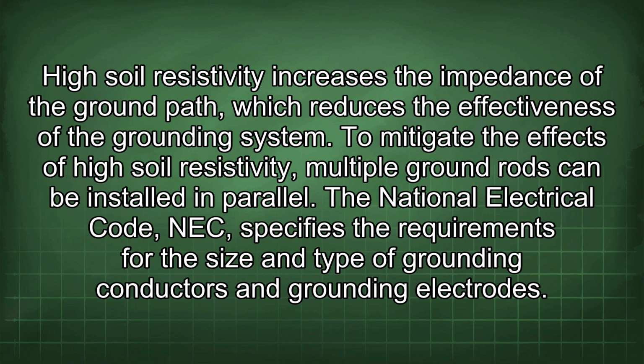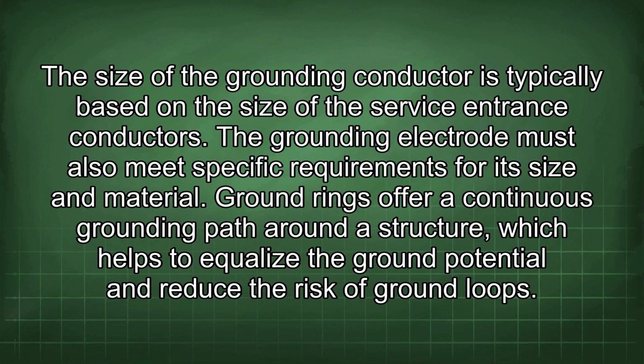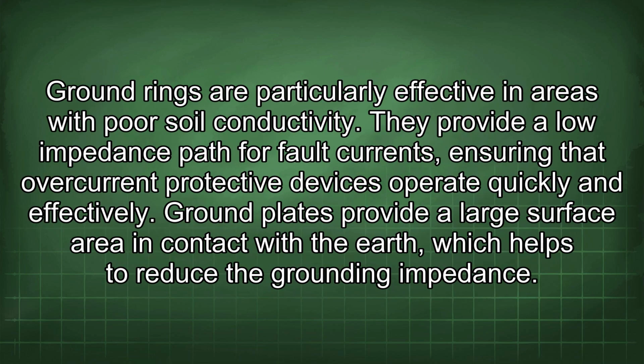The National Electrical Code (NEC) specifies the requirements for the size and type of grounding conductors and grounding electrodes. The size of the grounding conductor is typically based on the size of the service entrance conductors. The grounding electrode must also meet specific requirements for its size and material. Ground rings offer a continuous grounding path around a structure, which helps to equalize the ground potential and reduce the risk of ground loops. Ground rings are particularly effective in areas with poor soil conductivity. They provide a low impedance path for fault currents, ensuring that overcurrent protective devices operate quickly and effectively.